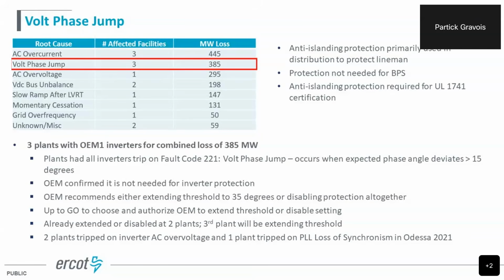The OEM has confirmed it's not needed for inverter protection. So they've recommended that you can either disable the protection altogether or extend the threshold. Right now it's set at 15 degrees. They can extend that out to the max of 35 degrees. The OEM verified in some simulations that if it was set at 35, this function would not have tripped for this event. But it's up to the GO to choose if they want to extend the threshold or disable it altogether, and they need to authorize the OEM to do that work.